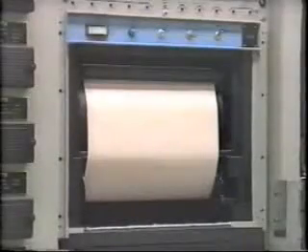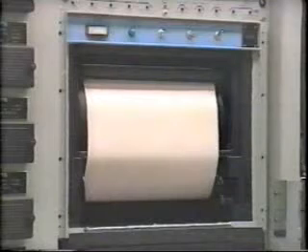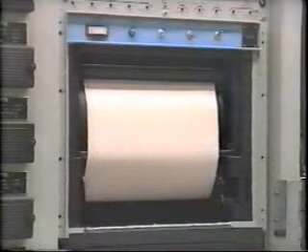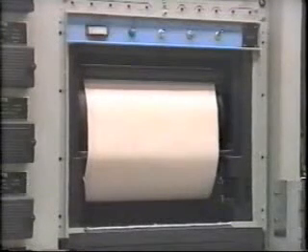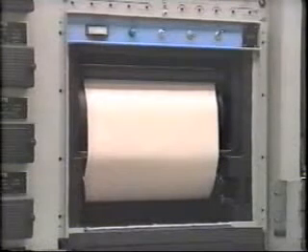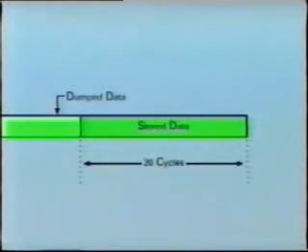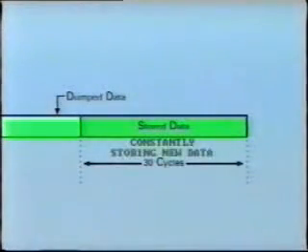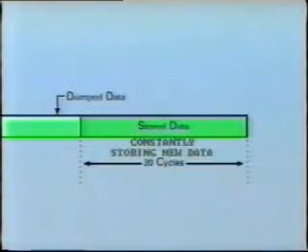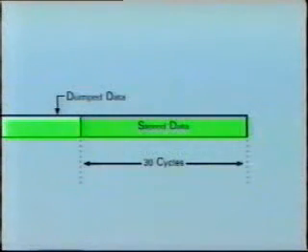Another type of recording system uses a pre-fault oscillograph. This machine has a built-in solid-state memory that can store several cycles of data, up to 30 cycles in some machines. The memory works in a recirculating fashion — at any instant, the memory stores the immediately preceding 30 cycles of data. As time goes on, the memory is constantly storing new data while dumping old data, but there's always 30 cycles in storage at any given time.